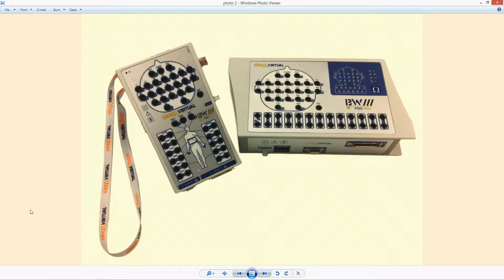The second system that I want to highlight is the BW3. This is our 50 channel EEG and PSG sleep study amplifier. As you can see in this image, we have both the head box and the amplifier. On the left hand side, we have the remote head box, and on the right hand side, we have the amplifier with dual inputs.